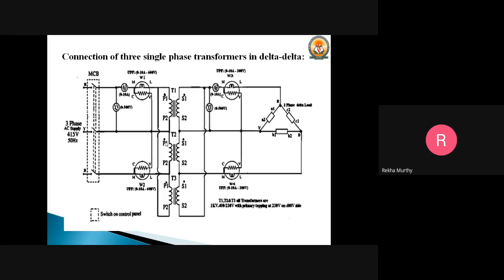So P2 is connected to P1, P2 is connected to P1, P2 is connected back to P1. That is how we are forming a closed loop. And on the other side, it remains as it is. Don't vary this. But here, what you have to think about is that in the delta to delta connection, you will definitely have almost 415 volts on the primary side. The same line voltage is also appearing on the primary side. So you have to prefer the primary side terminal that had 440 volts, and you have to consider that terminal as your P1 terminal.